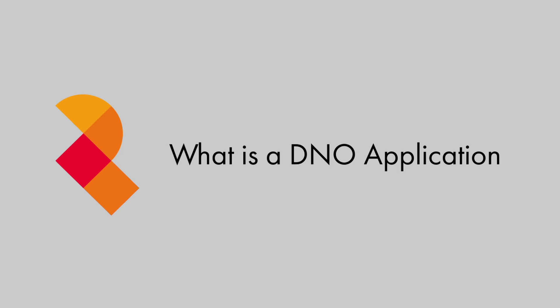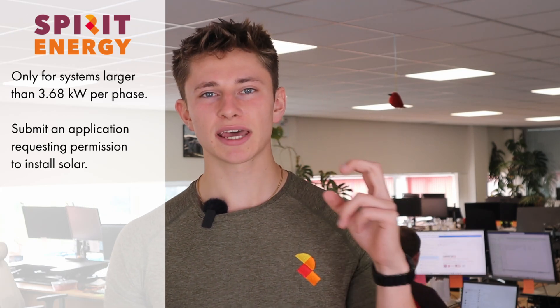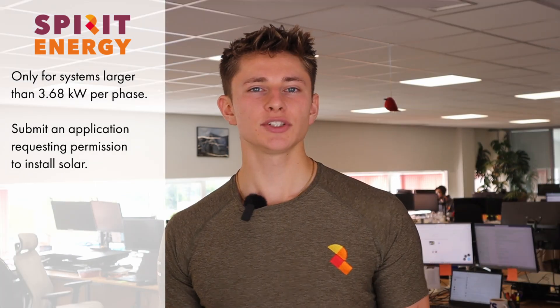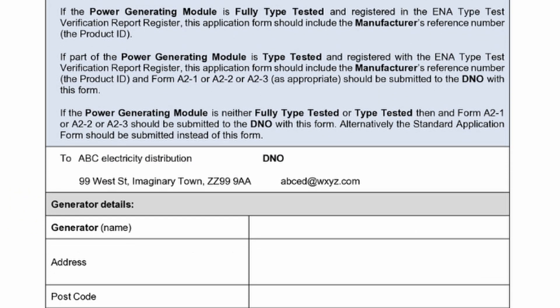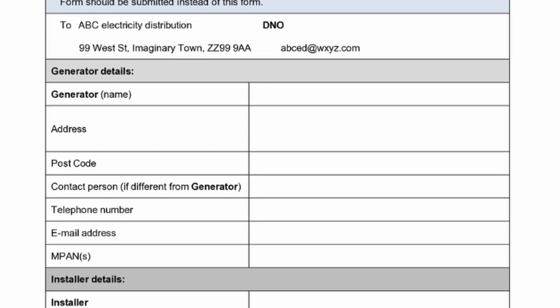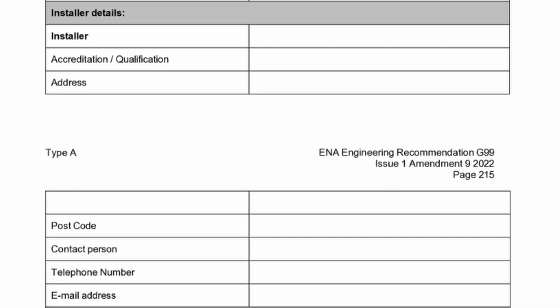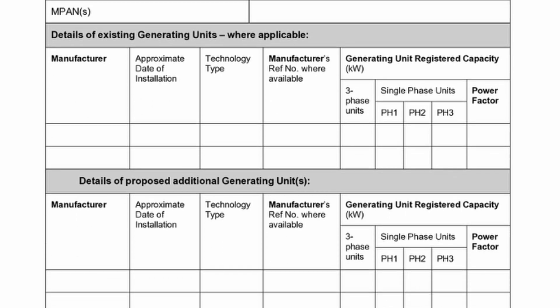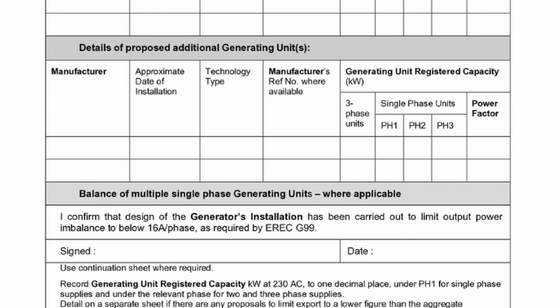When you install a solar or battery system larger than 3.68 kilowatts per phase, you need to submit an application to your local distribution network operator, or DNO. This is usually a G98 or G99 application. Most solar installers will do this application on your behalf, usually after you've settled on a final system design.